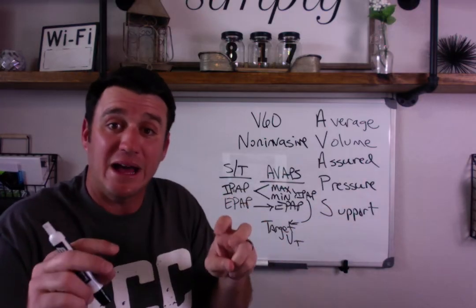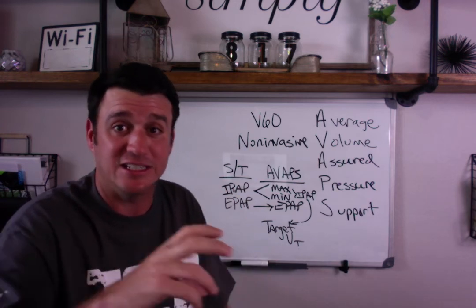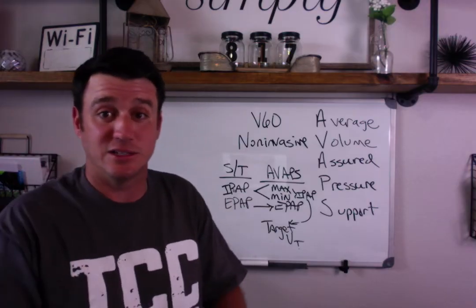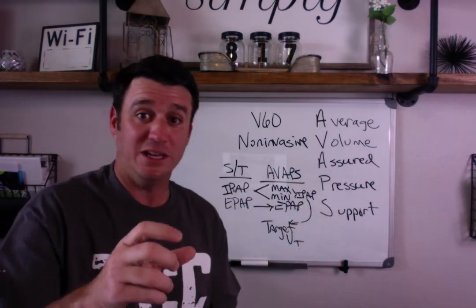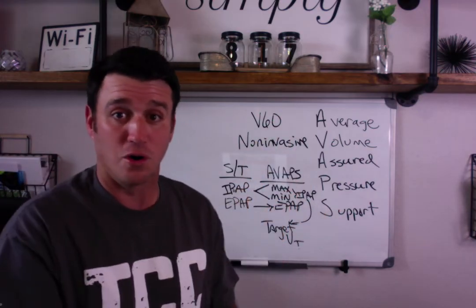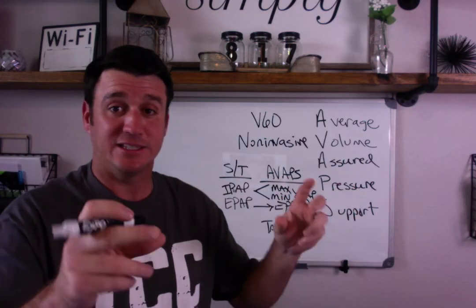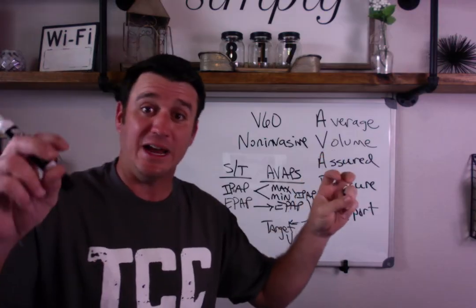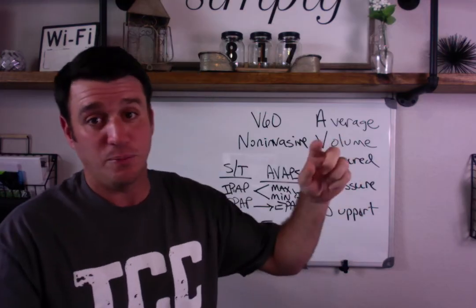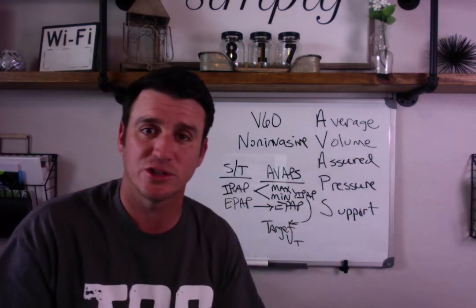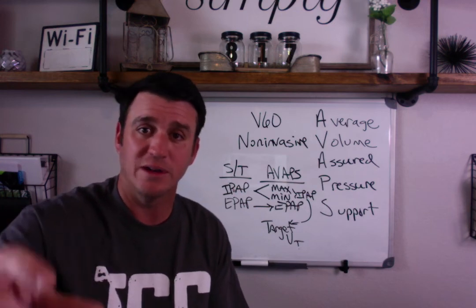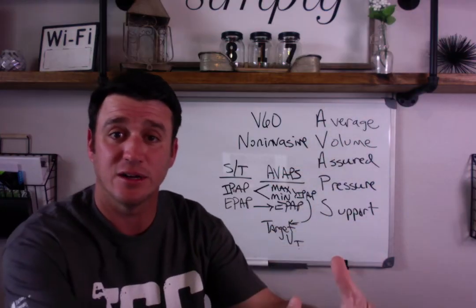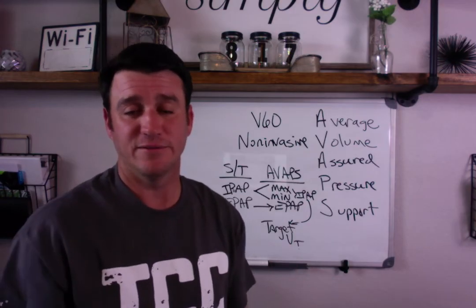Think about the same concept with AVAPS. You've got a little imaginary RT inside the V60 saying, 'Average tidal volume is too low — I need to increase IPAP because the target tidal volume has been set here.' Or, 'The average tidal volume is too high — turn the pressure down.' And it will adjust the pressure automatically without you being in the room, maintaining an assured tidal volume, which will hopefully equal an assured minute ventilation.